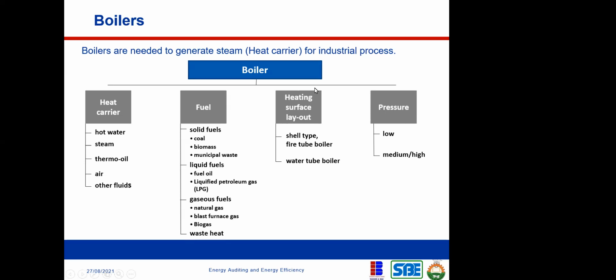So for boilers, you have heat carriers. Heat carriers are the things that actually carry that heat from the boiler to the point where you need to utilize that heat. Maybe you want to do a drying process. You want to dry a certain industrial raw material, and you need heat to go through that raw material to extract the moisture content. So these are the things that can carry that heat for you: water, hot water, steam, thermal oil. You can also use air or other fluid as a heat carrier.